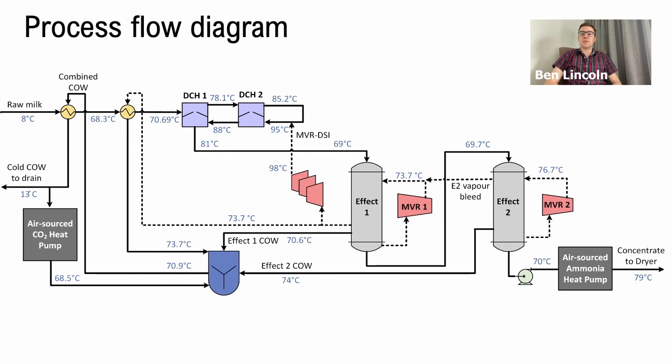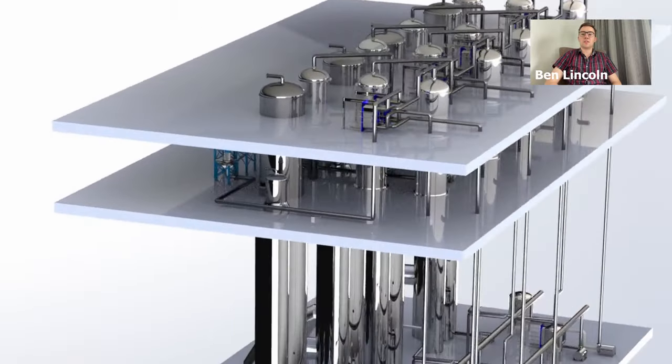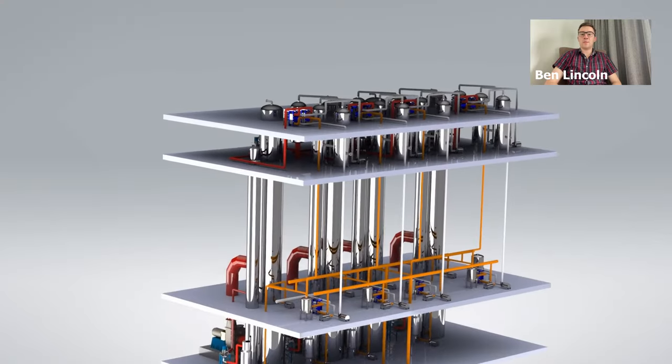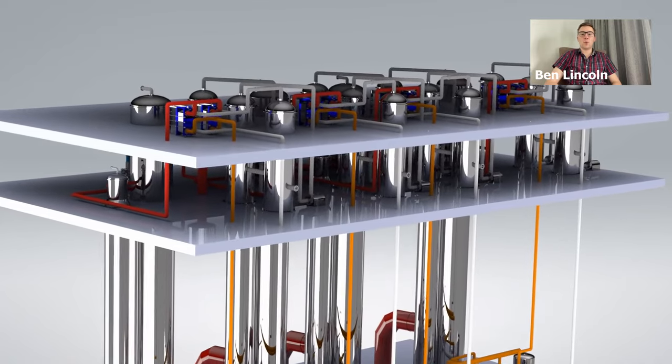The key features of this process design include the use of two direct contact heaters for fast heat transfer and process simplicity, as well as a three-stage vapor fan that upgrades excess vapor in order to substitute steam that would have been traditionally supplied from a fossil fuel boiler.